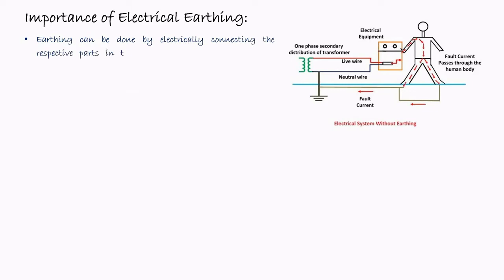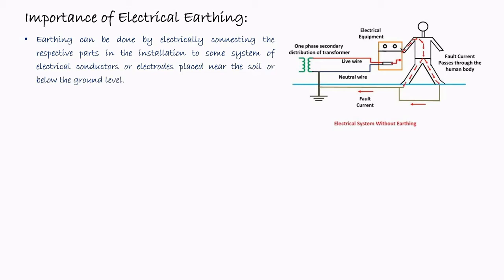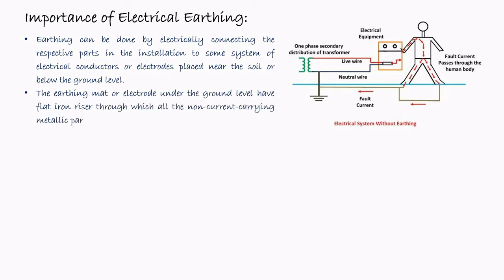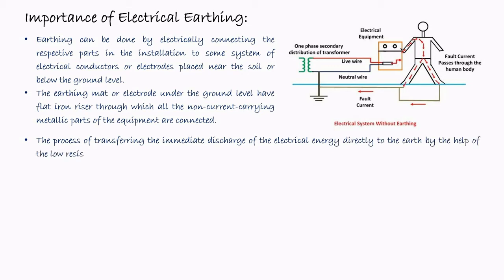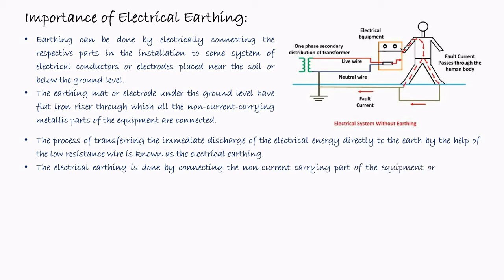Earthing can be done by electrically connecting the respective part of the installation to some system of electrical conductors or electrodes placed near the soil or below the ground level. The earthing mat or the electrode under the ground level has the flat iron riser through which all the non-current carrying metallic parts of the equipment are connected. The process of transferring the immediate discharge of the electrical energy directly to the earth with the help of the low resistance wire is basically known as the electrical earthing. The electrical earthing is done by connecting the non-current carrying part of the equipment or the neutral of the supply system to the ground that we have already discussed.